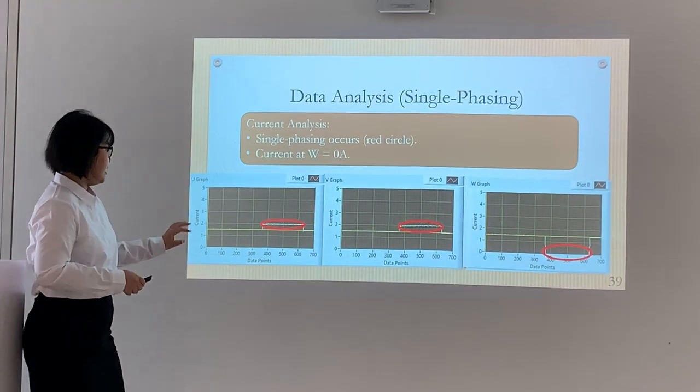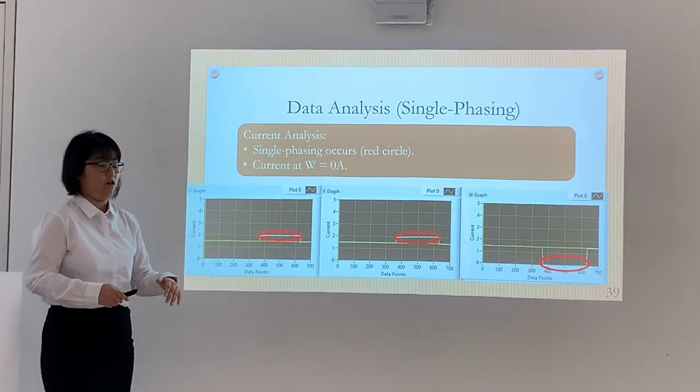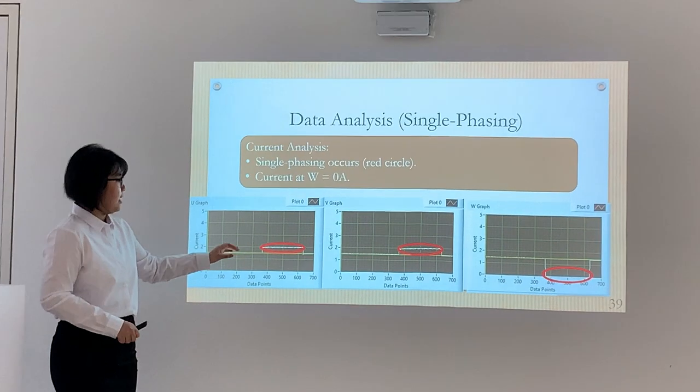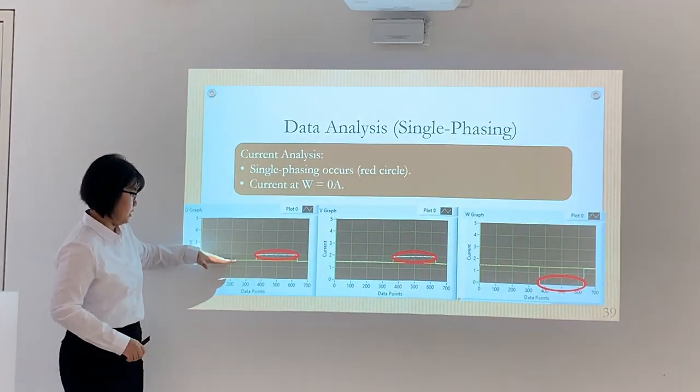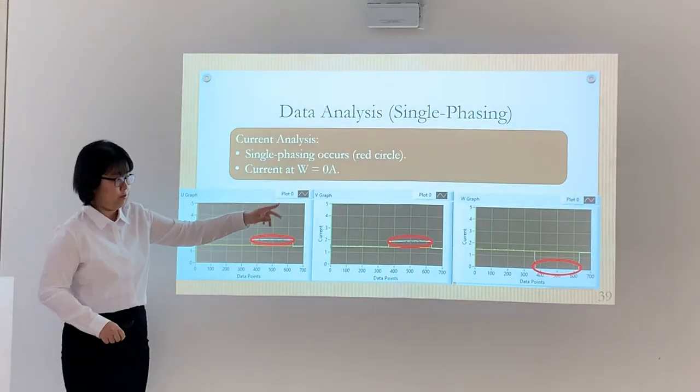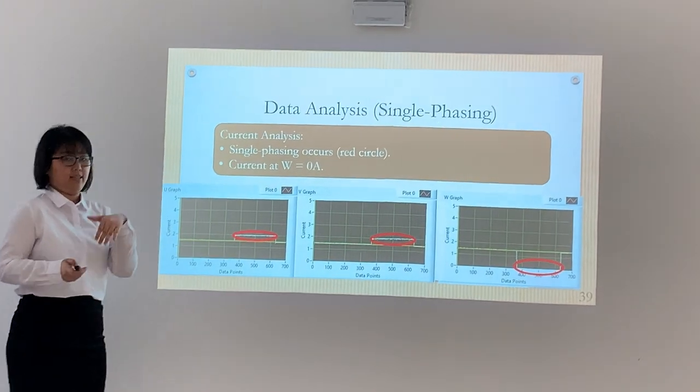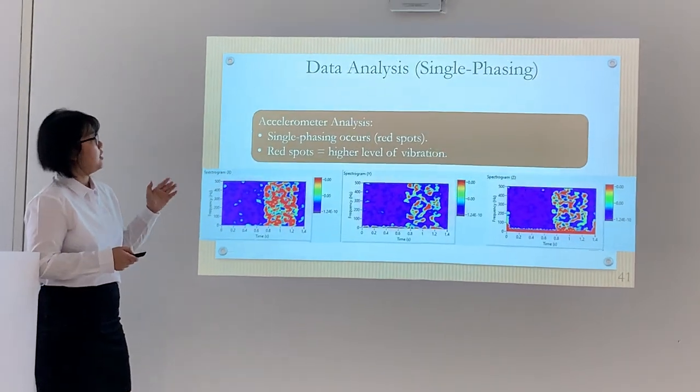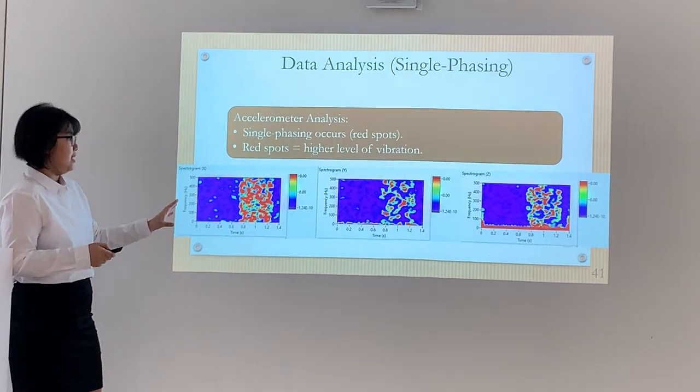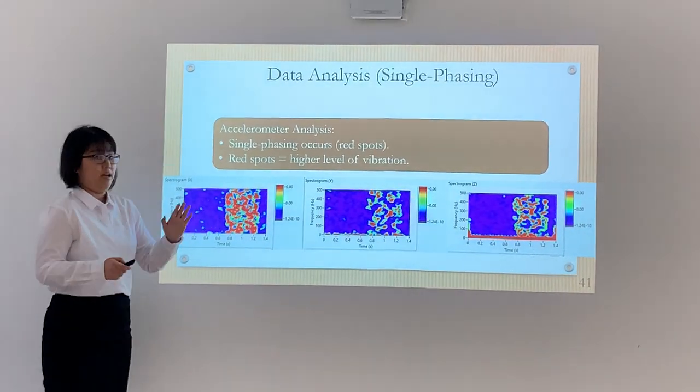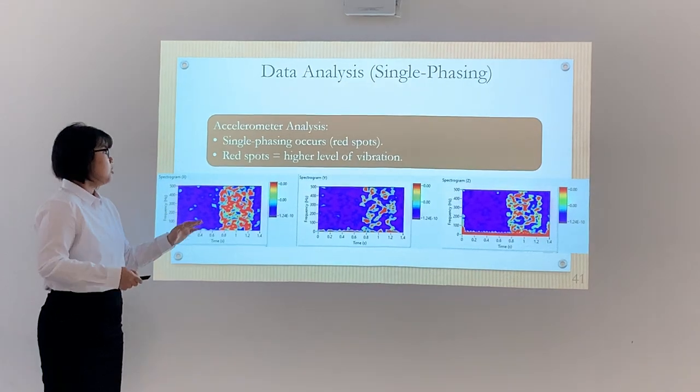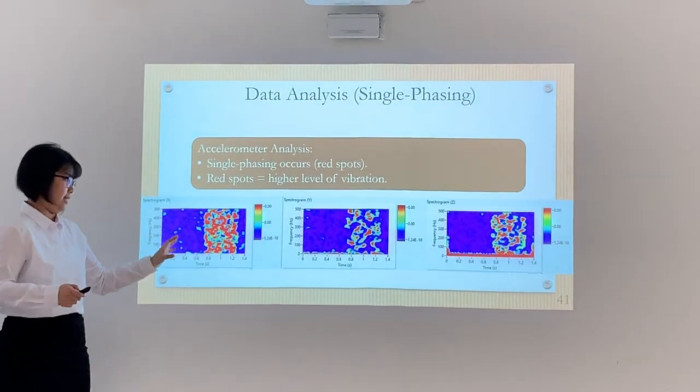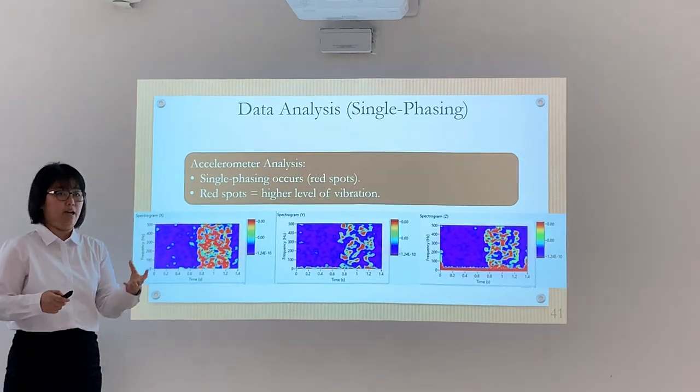These are the findings we got from our experiment. The red circles are where the fault occurs. This is U, V, and W graph. For U graph, initially the current was here and it spiked up when W goes to zero. This is where single phasing occurs. This is the spectrogram for single phasing. The red spots are where the fault occurs, meaning higher amplitude there.